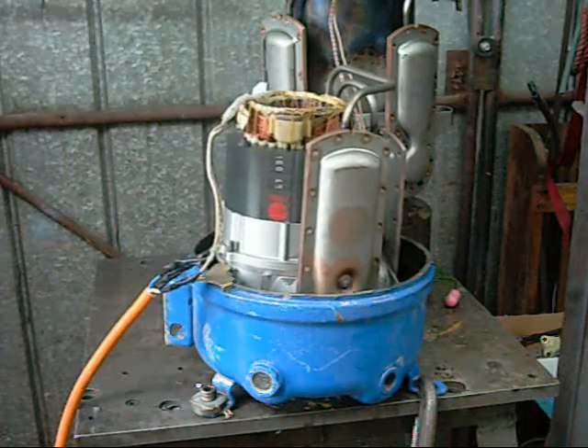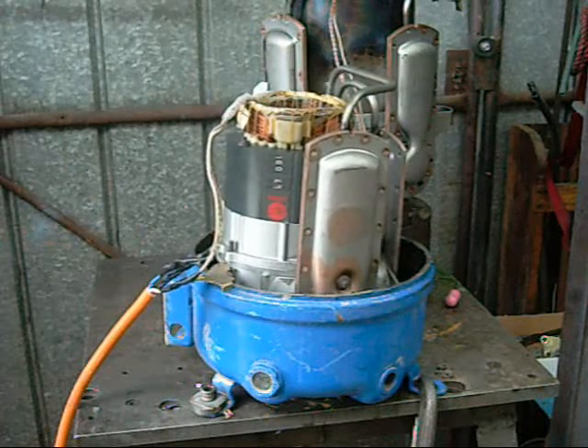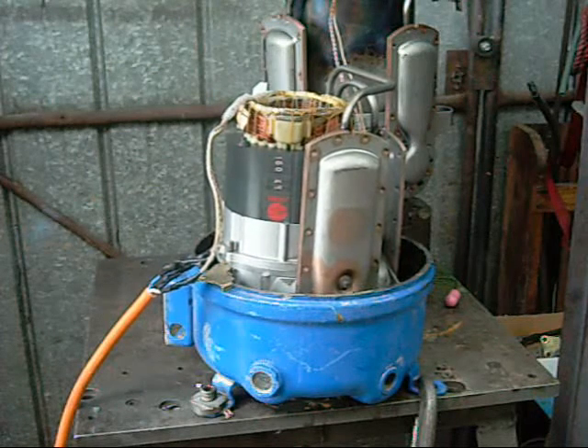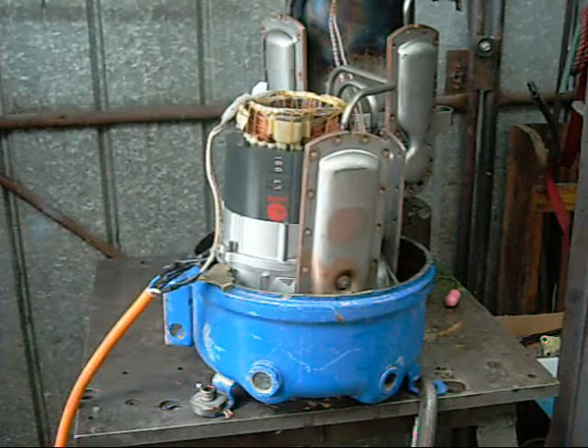There's a point there where the drive cuts out — I go too high and she cuts out and limits the current. It just suddenly goes from 6 amps to 12 amps and then beyond, so definitely no good idea to run it too long at that speed. But without oil, I suspect a failure would be very quick, very very quick.